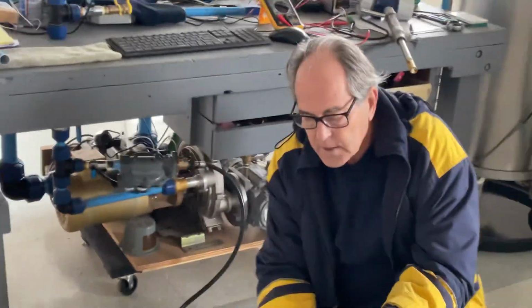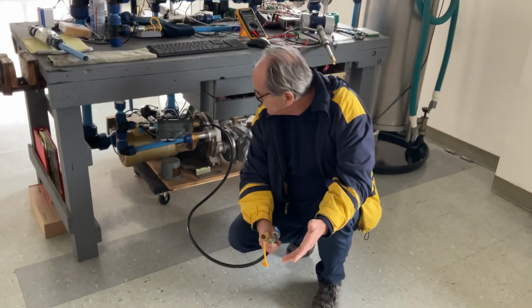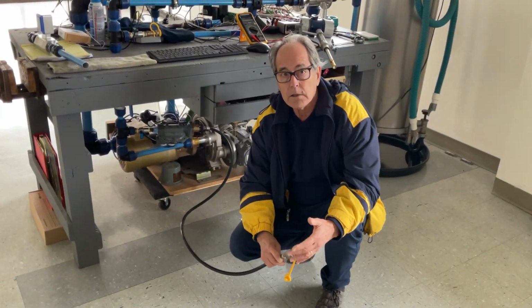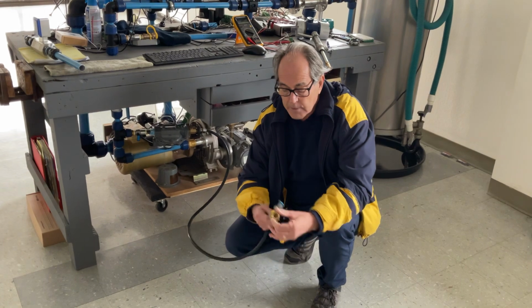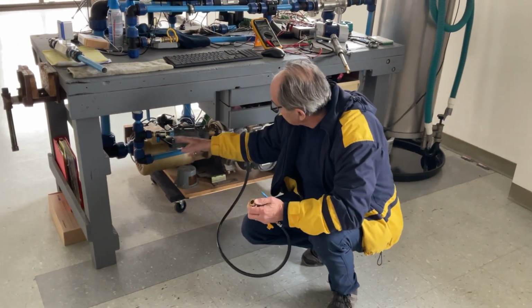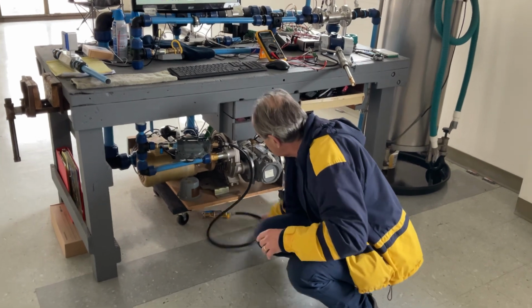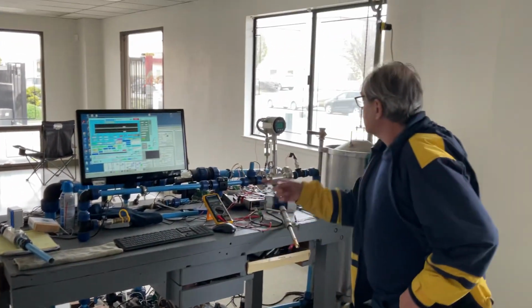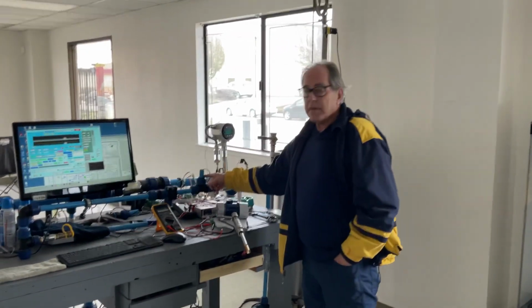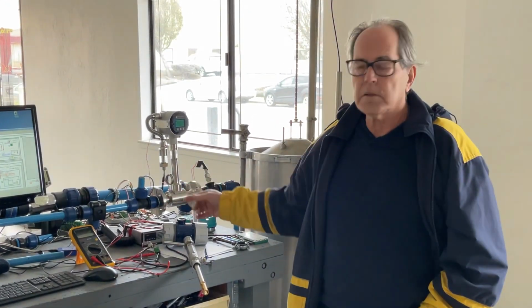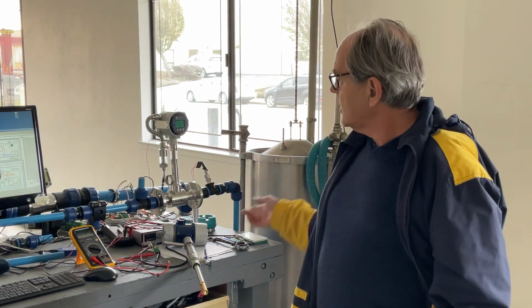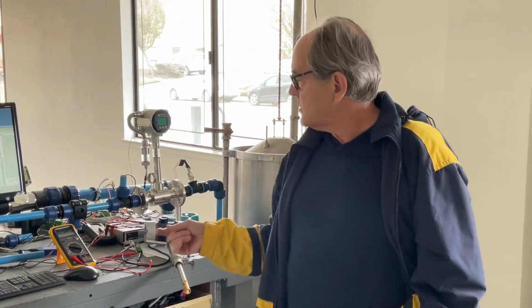So we'll put methane, hydrogen, argon, helium, whatever. We'll fill it up, it goes through the regulator, we'll fill the entire system, and have that gas flowing in the entire system. And here's a methane sensor that'll tell you the concentration of methane, oxygen, other components. So we have another sensor that can tell you what the gas composition is.